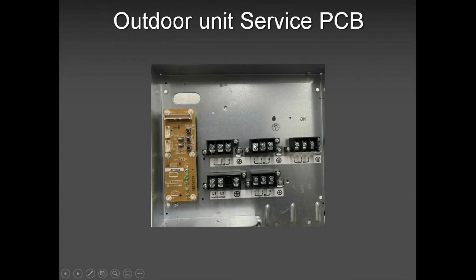Well, the winding is in good shape, but the compressor got frozen. I mean, got seized. Mechanically got seized. And how we have found out in most cases is when the unit was not charged correctly, or there was a leak and it was not fixed, and the compressor lost all the oil, and the unit kept running.